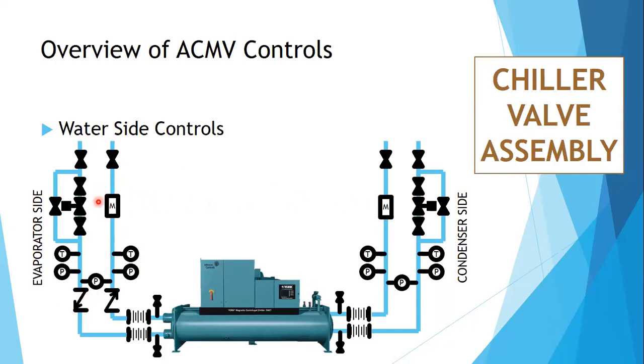Before, it's not common to put a metering device on the chiller, but now it's very common to put a metering device on your chiller, kind of like the balancing valve. But the difference is it doesn't restrict the flow, but only measures the flow. The balancing valve also measures the flow through pressure difference, but the metering measures the flow to ensure the chiller's efficiency. The control valve also measures the. Yes, sir. Any question? No question? All right. So based on the metering valve, based on the water flow rate going through the chiller, your control valve opens and closes as necessary.